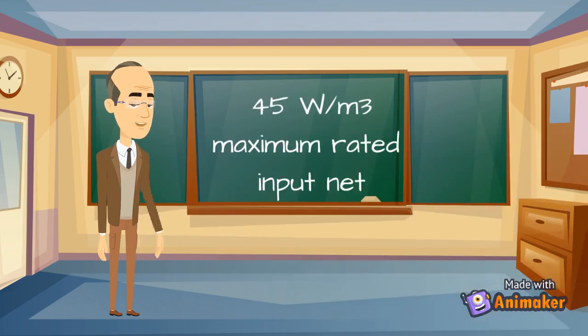For a space heater in a room the maximum appliance rated input net is 45 watts per meter cubed. This means for every cubic meter of the room size a maximum of 45 watts input can be used.